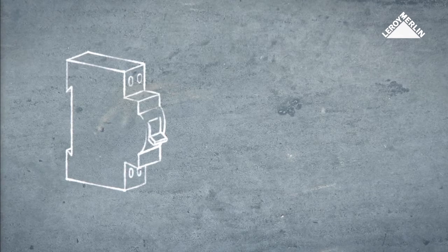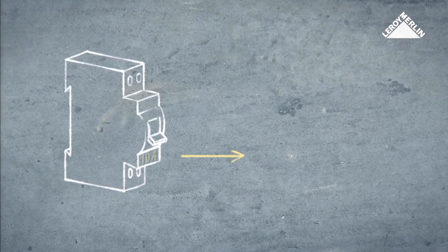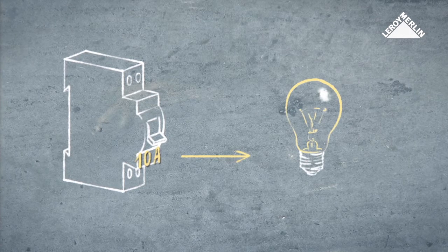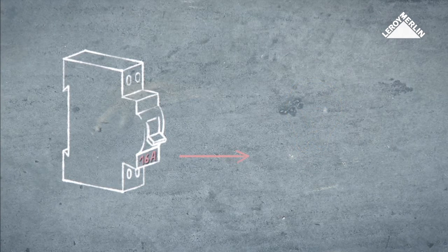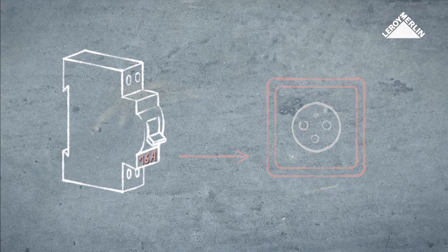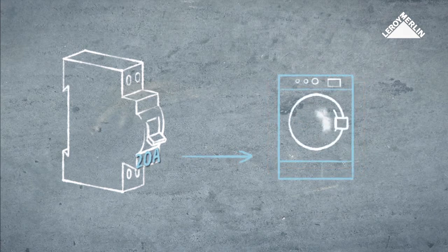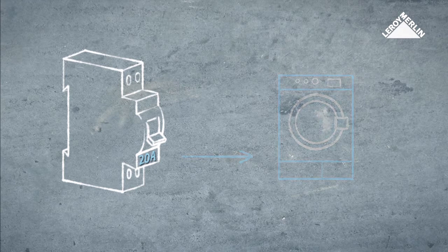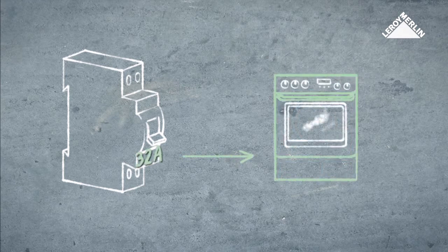The rating of each RCD depends on the type of circuit it has to protect. Lighting circuits require 10 amps. Circuits requiring 10 to 16 amps have 16 amp RCDs. For a washing machine, dishwasher, water heater, tumble dryer and oven, the rating is 20 amps. For a hob and electric cooker, the rating is 32 amps.